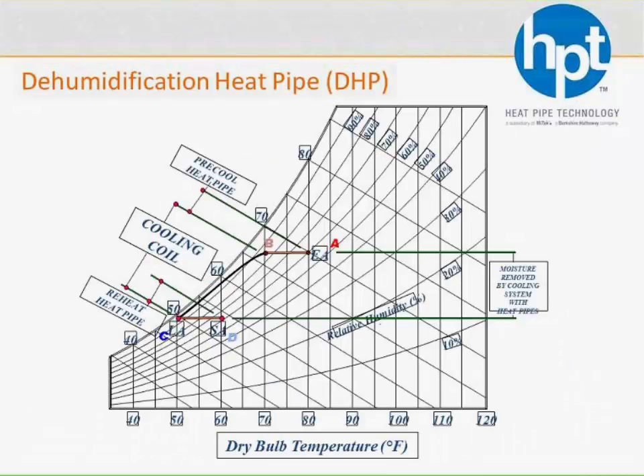So if we look at that same circuit on your psych chart here, you can see that if we didn't have a heat pipe on it and you had 80-degree air coming in and you had to get 50 degrees off the cooling coil, you'd have to have enough cooling capacity to go from point A all the way down to point C. But if you put a wraparound heat pipe on it, then now we're doing some pre-cooling for you. So now we're going to cool down from A to B. So now that cooling coil, instead of seeing 80-degree condition A, is going to see 70-degree condition B, and you don't need as much cooling capacity to get down to that 50-degree dew point now. And then, of course, whatever that pre-cool heat is just being wrapped around and being used as the free reheat from C to D.